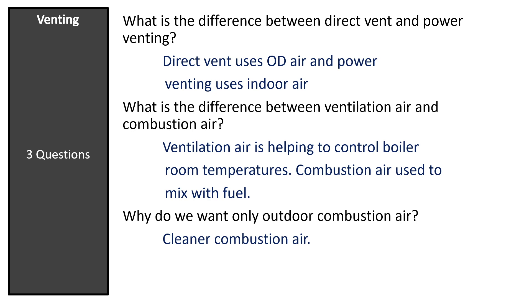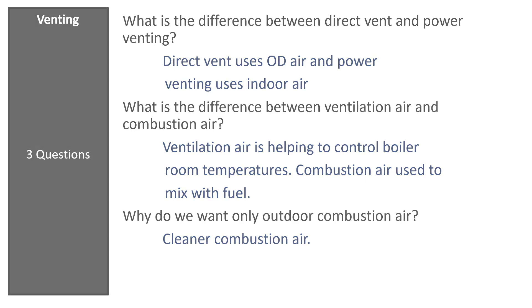The difference is: direct vent means two pipes to the outside — one for venting the products of combustion, the other for air intake. Power vent is one pipe to the outside for venting products of combustion, and indoor air is used from the structure. As homes become tighter and boiler rooms become smaller, using outdoor air will supply the boiler with the proper amount of clean combustion air.